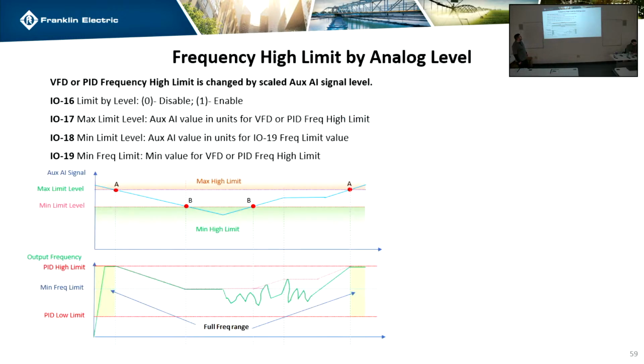All right, go to the next one. This is an explanation of what we were just talking about with the frequency limit. This is what it looks like on the chart. So you got 4 settings. You have enable. You have the value in units for the PID frequency. And then you have your limit for your low limit and your high limit.